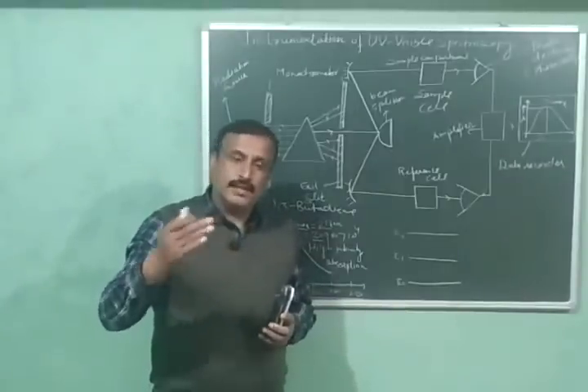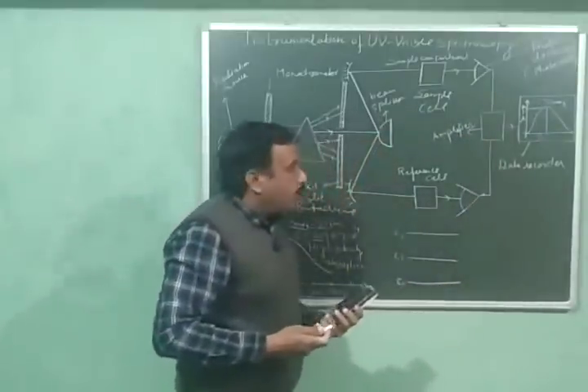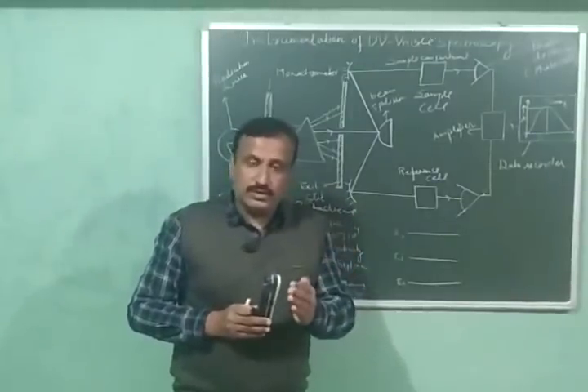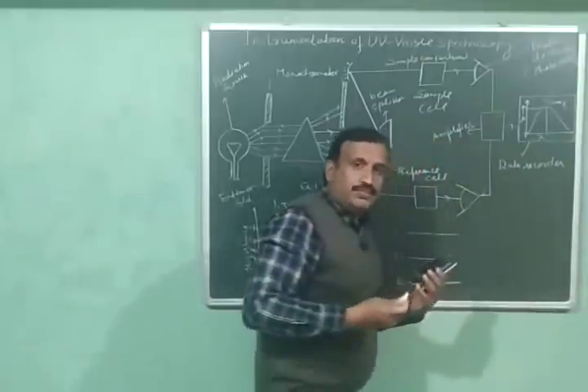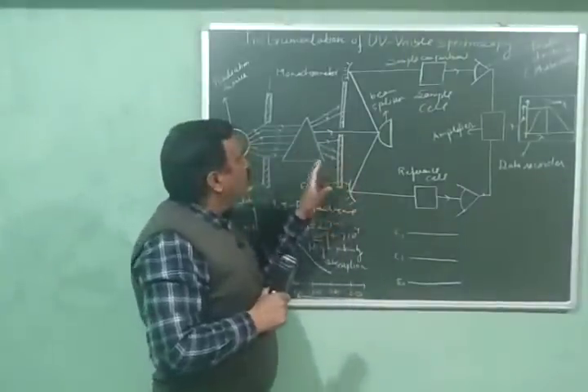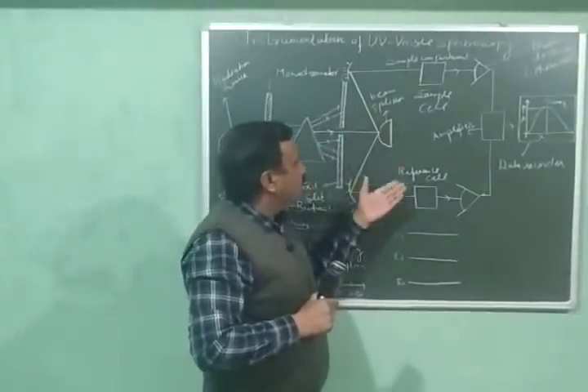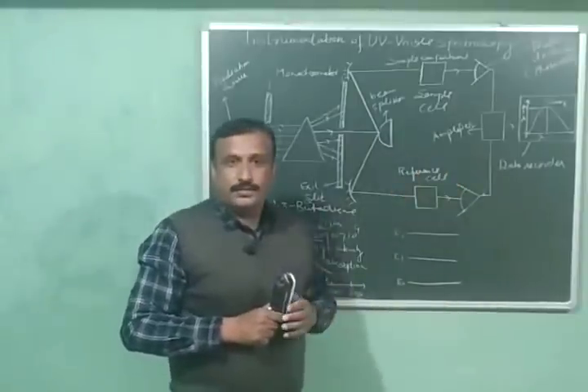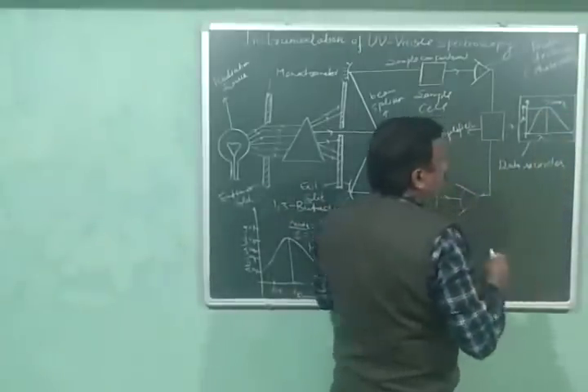All these measurements are made in the form of electric signals, which are passed to the amplifier. The amplifier amplifies the signal, and the data recorder finally records the absorbance as a function of wavelength in the form of a graph — with wavelength along the x-axis and absorbance along the y-axis. Radiations of different wavelengths are selected from the exit slit of the monochromator, passed through the cells, and their absorbances are recorded.